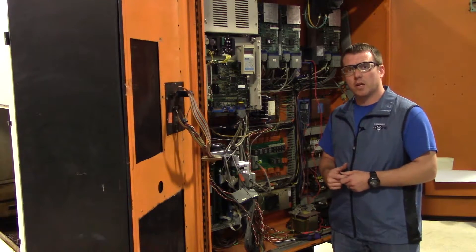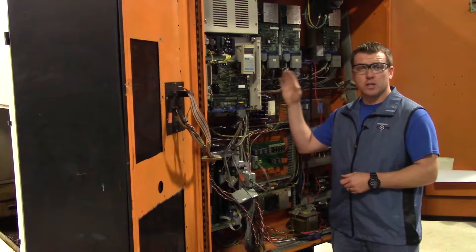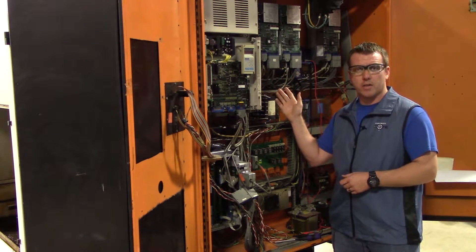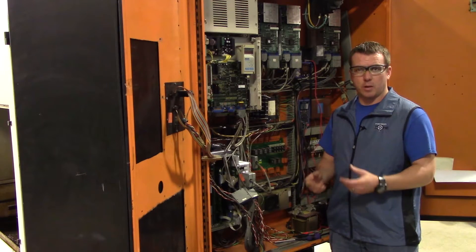Even though I have the machine locked out, tagged out, I'm going to make sure I check the RSTs and UVWs on the drive that I'm working on. That way, we'll just double verify power.